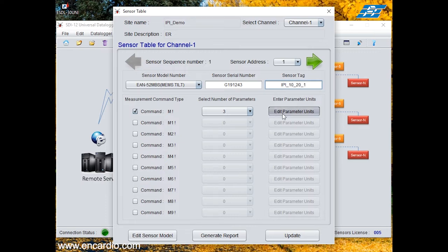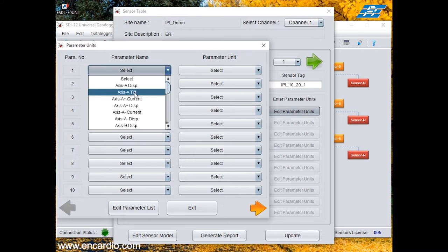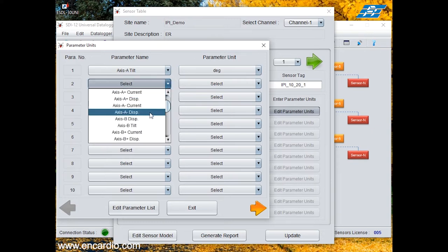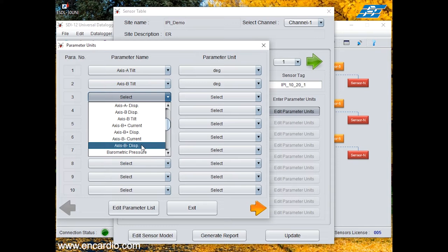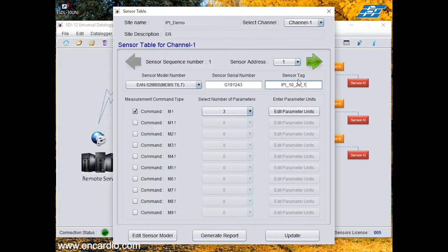Click on edit parameter unit. You need to select the parameter name as axis A tilt, parameter unit degrees. Since it's a biaxial sensor, you need to select the second axis, axis B tilt, parameter unit degree. Then the third parameter name is temperature, unit is degree centigrade. Click on exit. Then click the next arrow, sensor address 2 would be displayed.